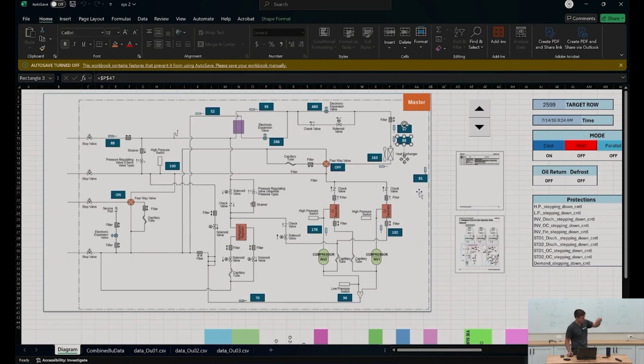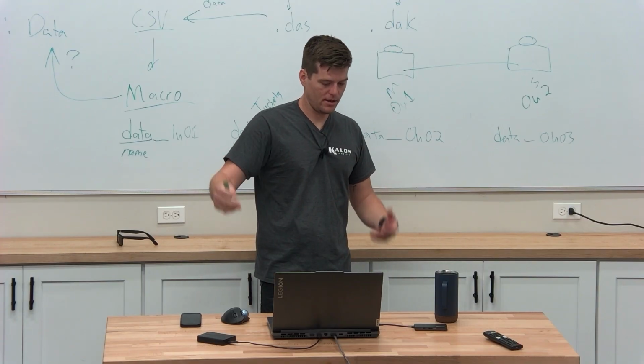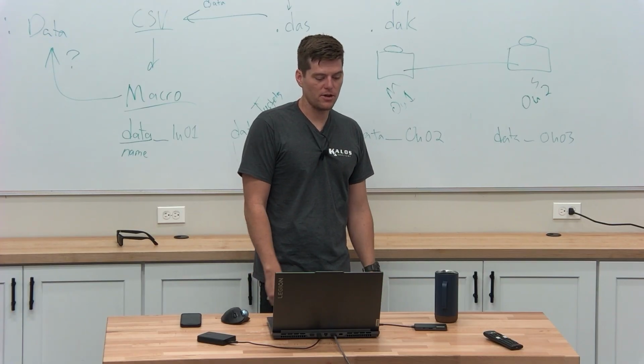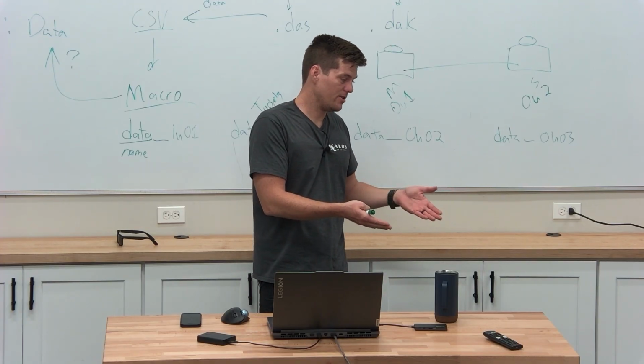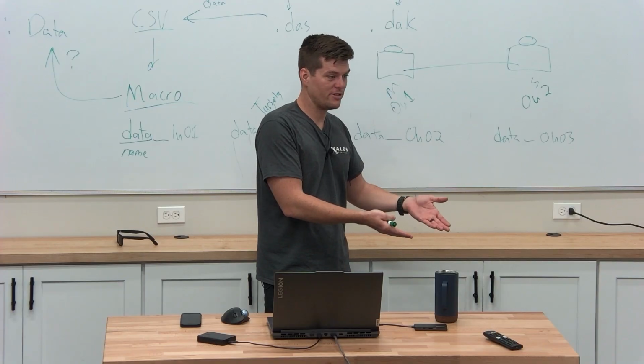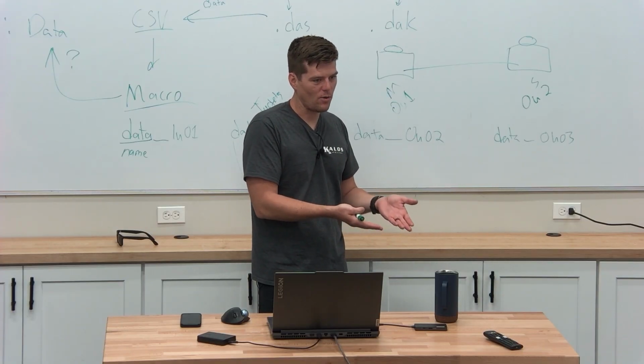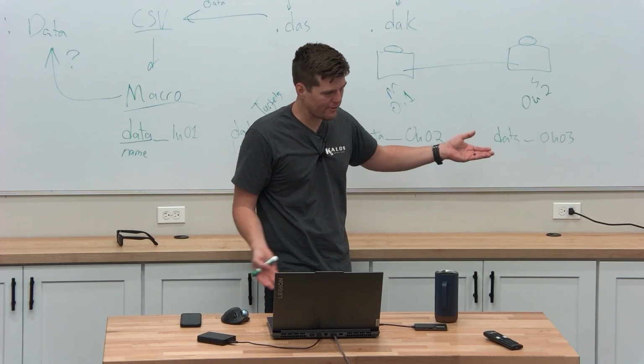Like, I don't have to go through the line items. But this is how you find the problems that you can't see in Service Checker, right? The unit keeps pumping itself down, like the problem that we had on that one unit, where it's like, okay, my suction pressure is 23 degree saturation temperature, right? Why is it so low? Why is it freezing? Why is the whole line frozen? Right?